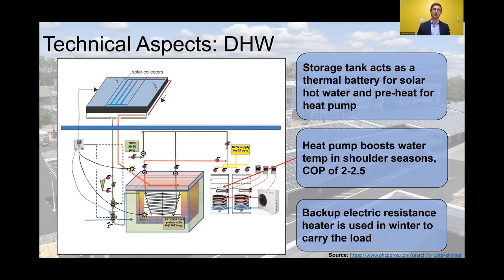So they use an air-to-water electric heat pump that has a coefficient of performance between 2 and 2.5. So this means that every kilowatt of energy that you put in, you get 2 to 2.5 kilowatts worth of heating. This is important because that's 2 to 2.5 times how efficient electric water heaters heat. Unfortunately, they don't work so well in the winter when the outside temperatures are really cold. So that's why you have a standard resistance electric water heater back things up, and then it shoots out and gets distributed to the apartments.